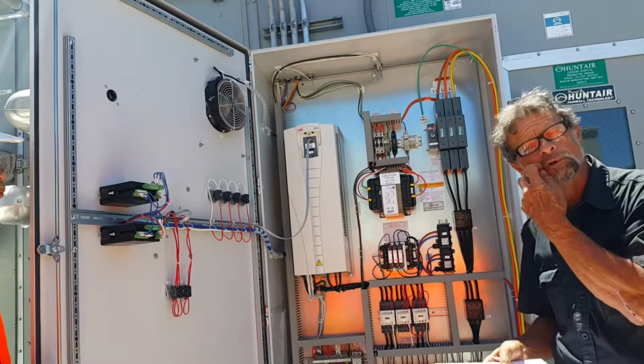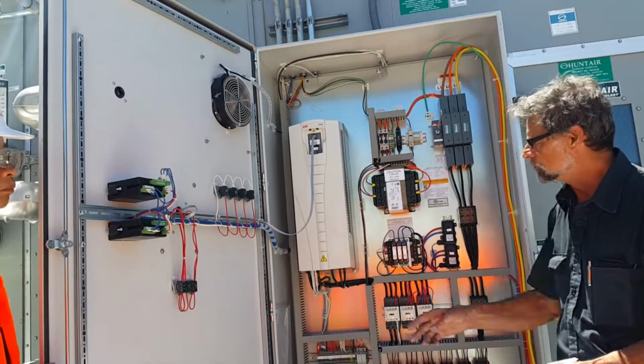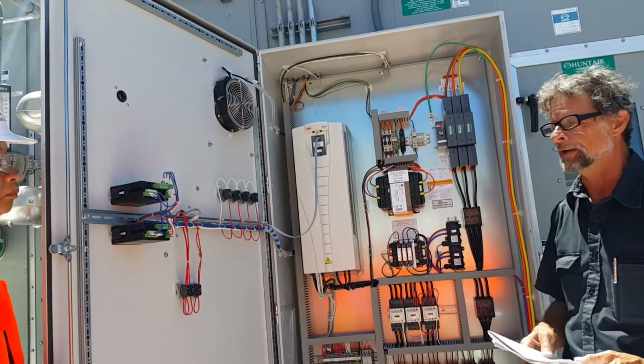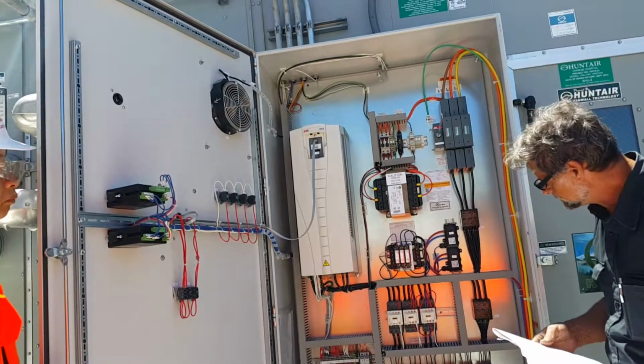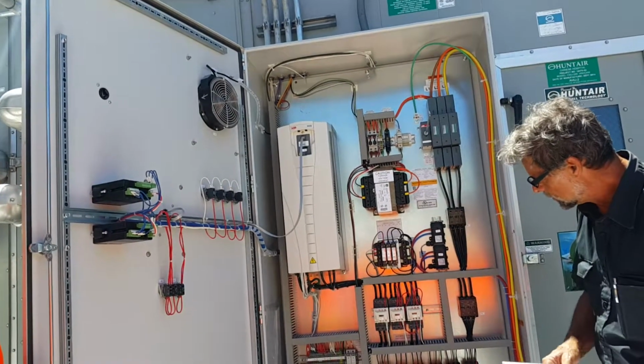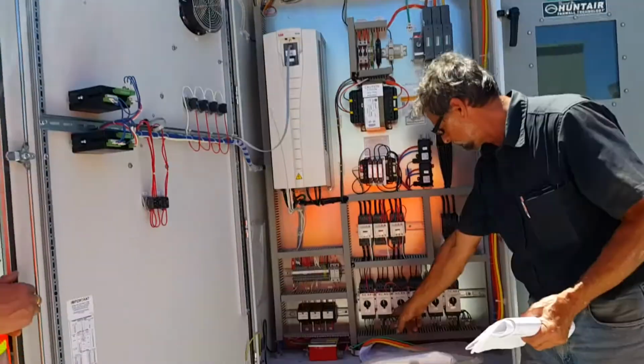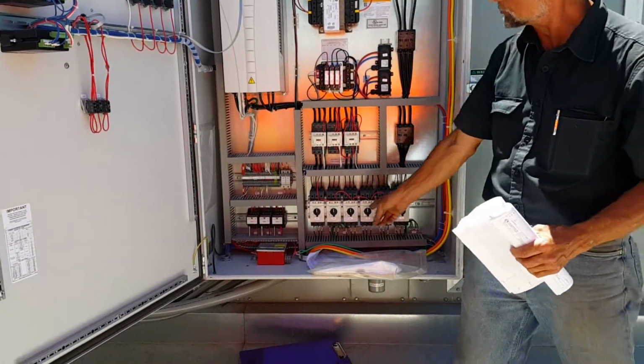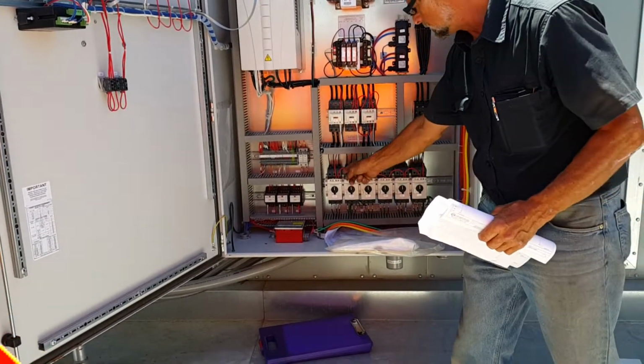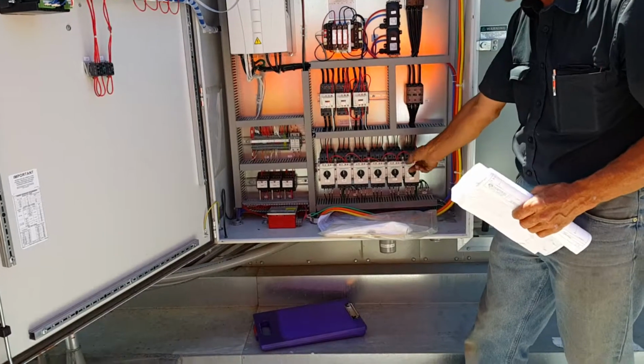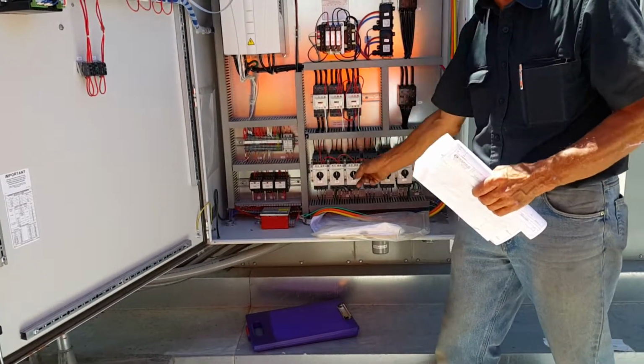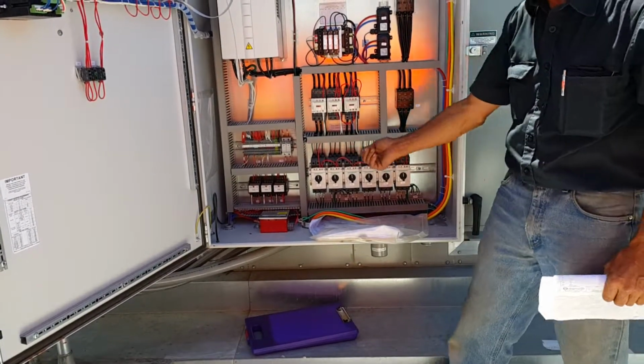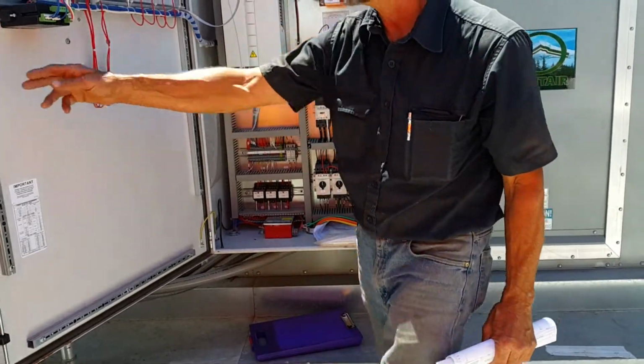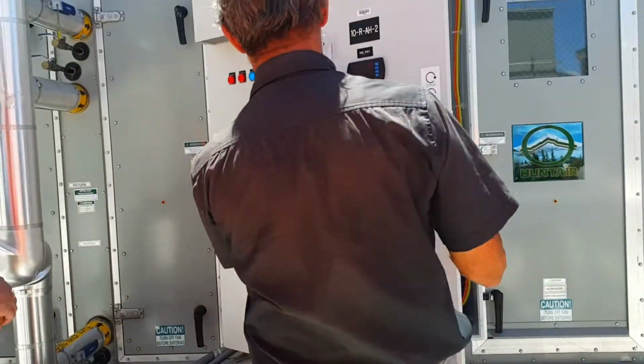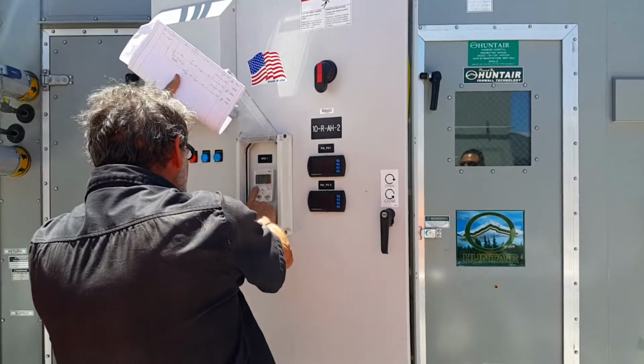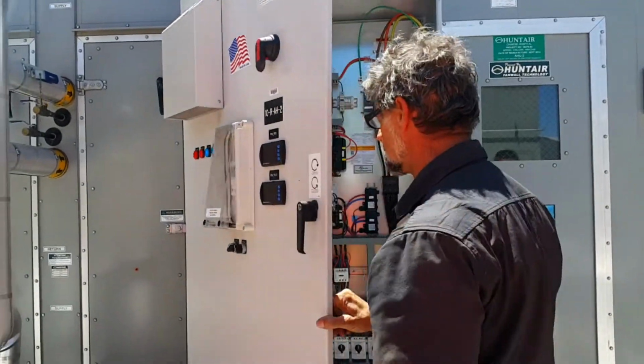A unit with dual drives on it, you just switch over to the other drive and you'll have full capacity. In this case, 6 motors in here. Each one has a circuit breaker. Each one has a contact that says the circuit breaker is in place right now in the on position. If one of these motors trips, I still have this off. It's still off.